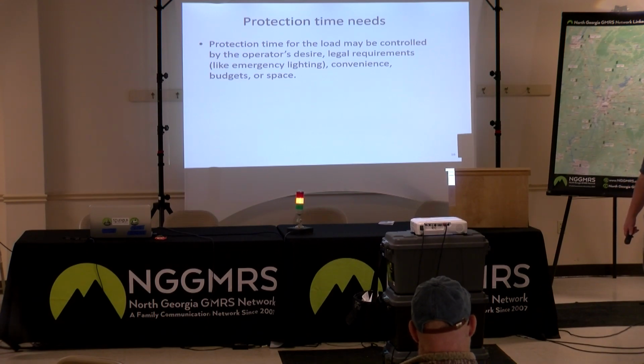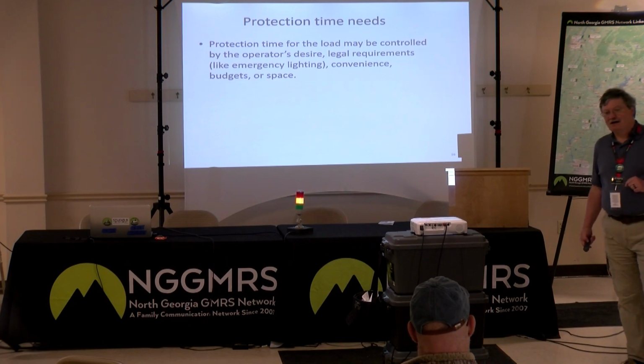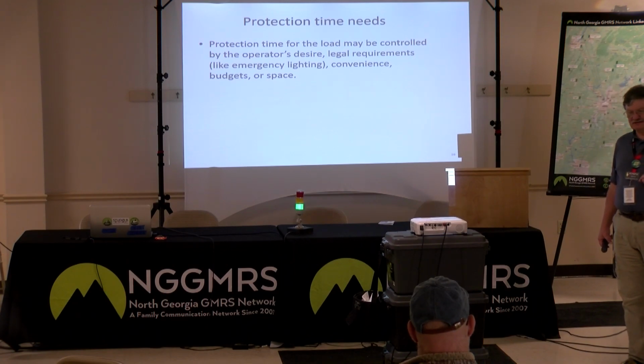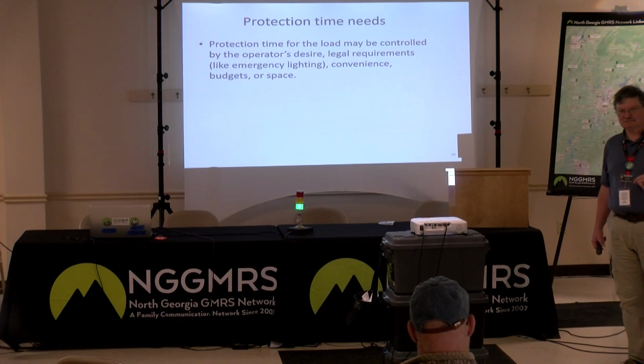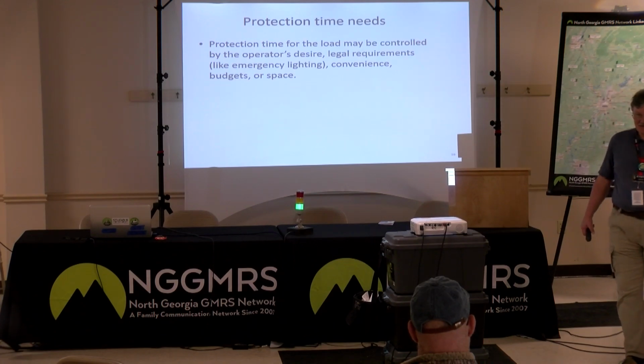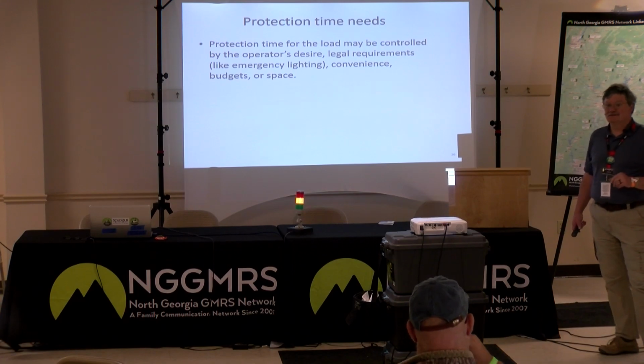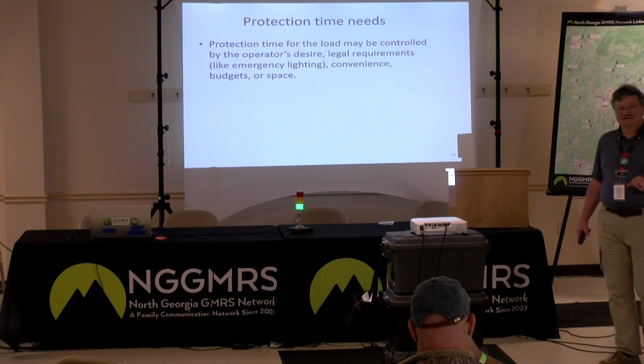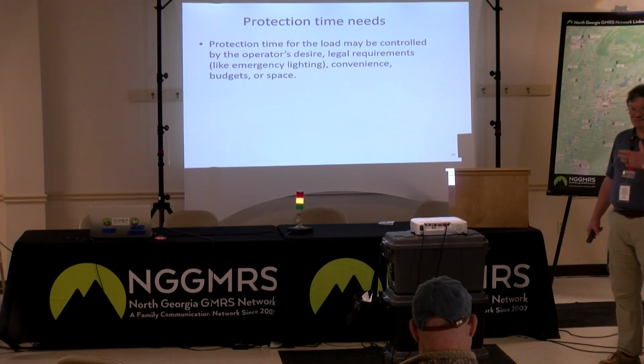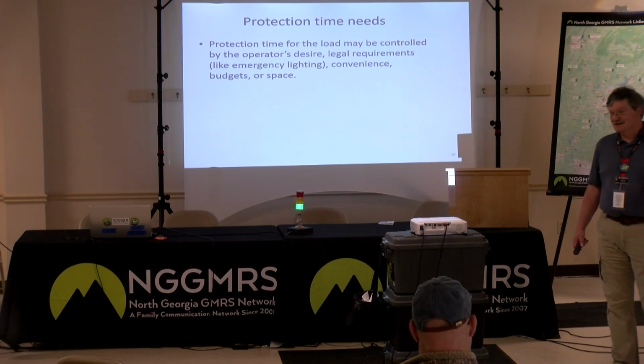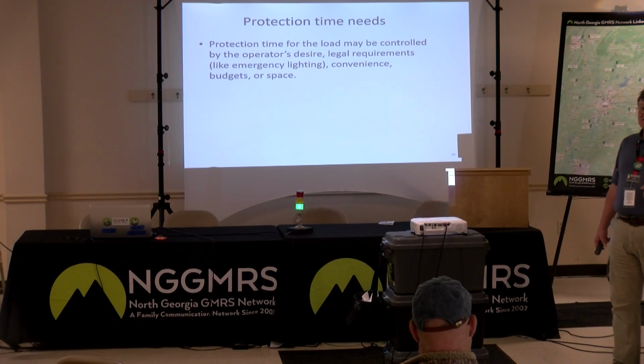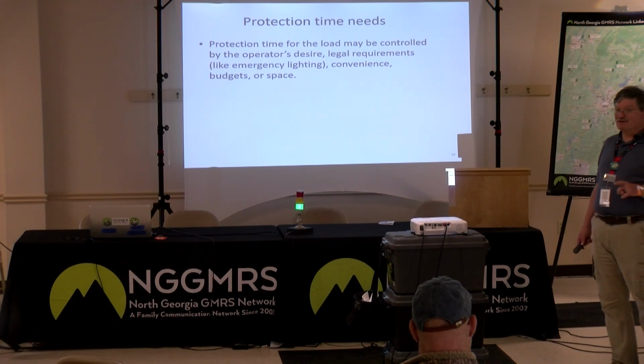You'd be surprised how big battery systems can get when you start talking about long protection times with substantial amounts of power. And when I'm saying substantial, I'm talking about needing 250 kilowatts for 2 hours. I've been working on a project, and that's the size of battery they're going to need. People are scratching their heads because I'm not the designer, I'm reviewing the design. And I said, guys, y'all need to look at your battery space — I think your battery is going to be bigger than the space you've allotted.